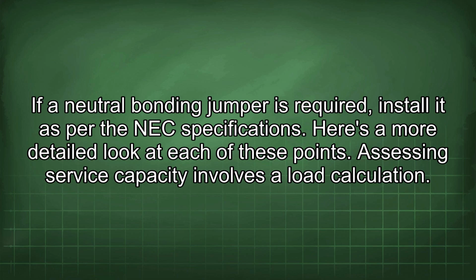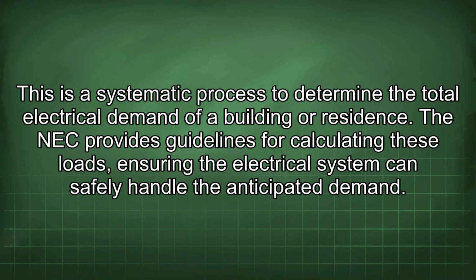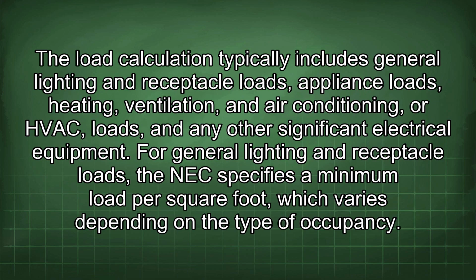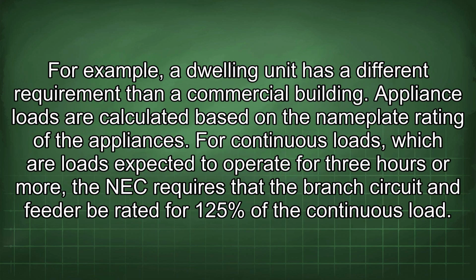Assessing service capacity involves a load calculation. This is a systematic process to determine the total electrical demand of a building or residence. The NEC provides guidelines for calculating these loads, ensuring the electrical system can safely handle the anticipated demand. The load calculation typically includes general lighting and receptacle loads, appliance loads, heating, ventilation, and air conditioning, or HVAC, loads, and any other significant electrical equipment. For general lighting and receptacle loads, the NEC specifies a minimum load per square foot, which varies depending on the type of occupancy. For example, a dwelling unit has a different requirement than a commercial building.